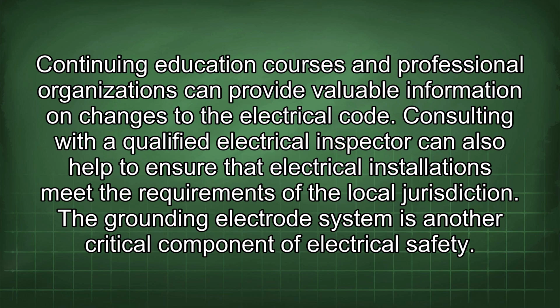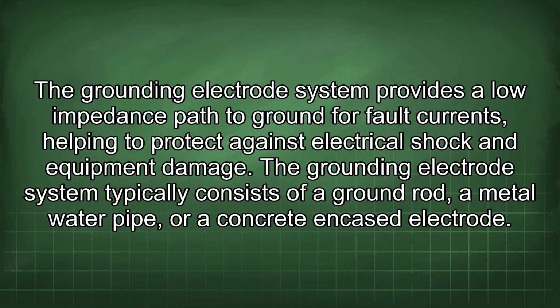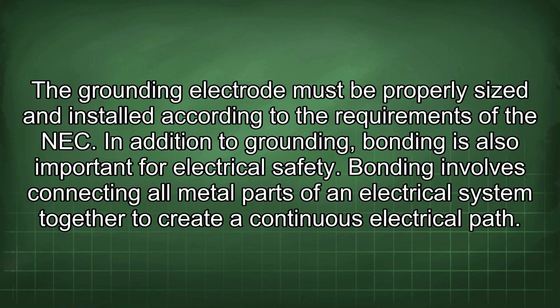Consulting with a qualified electrical inspector can also help to ensure that electrical installations meet the requirements of the local jurisdiction. The grounding electrode system is another critical component of electrical safety. The grounding electrode system provides a low impedance path to ground for fault currents, helping to protect against electrical shock and equipment damage. The grounding electrode system typically consists of a ground rod, a metal water pipe, or a concrete encased electrode. The grounding electrode must be properly sized and installed according to the requirements of the NEC.